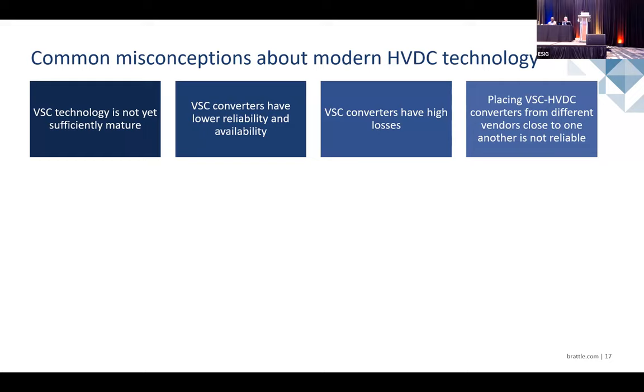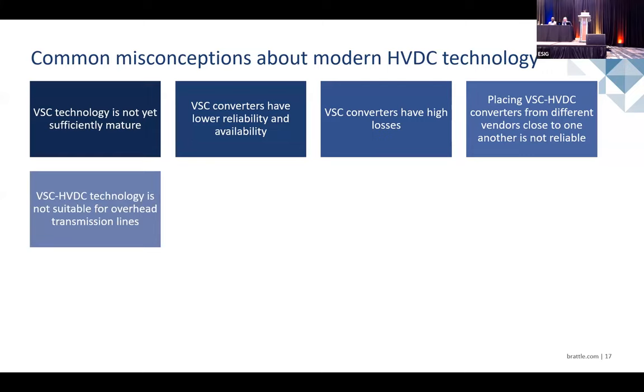Another misconception is that placing converters next to each other is not reliable. Of course, this particular thing is not measured, but we are gaining commercial project experience. There were a couple of projects where converters are placed next to each other, and a lot of studies were done, and the control system was improved and slightly modified, and they are in operation. We are gaining experience in that as well. VSC technology is compatible with overhead lines, and VSC HVDC can restart when there is a fault. You shut down and come back, like auto reclosing, the same as AC systems.